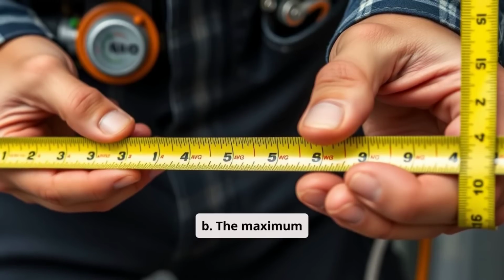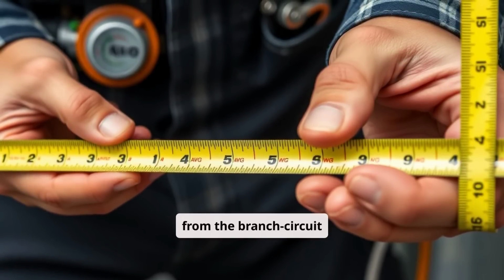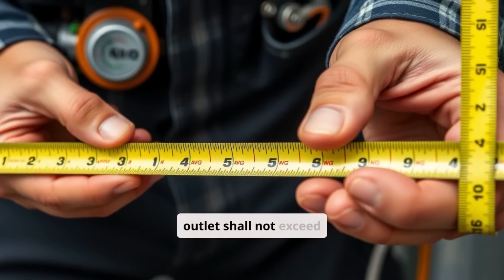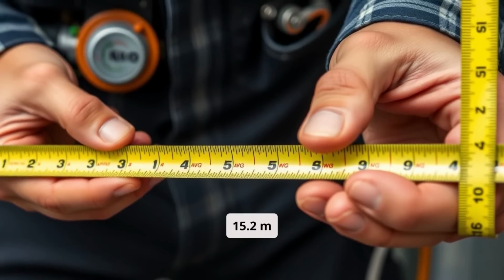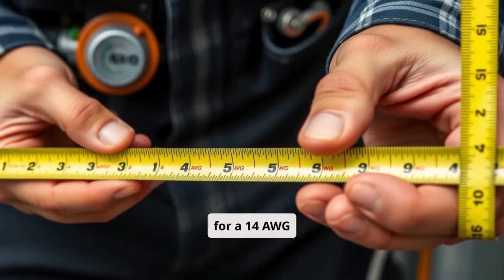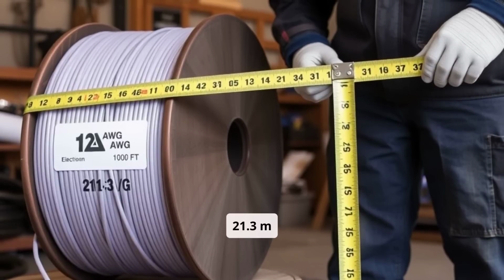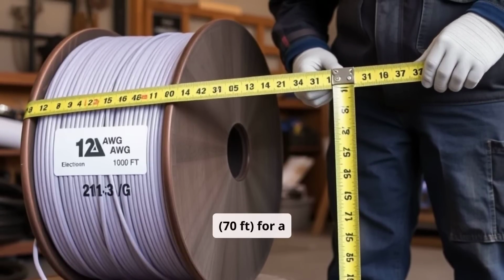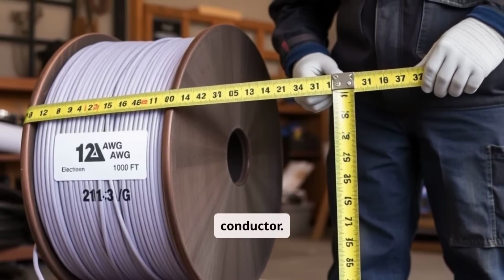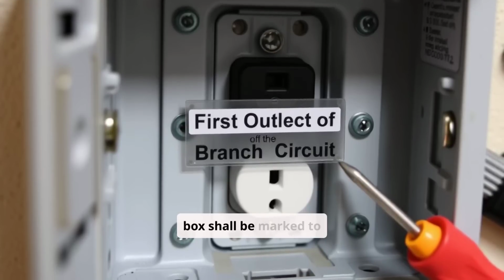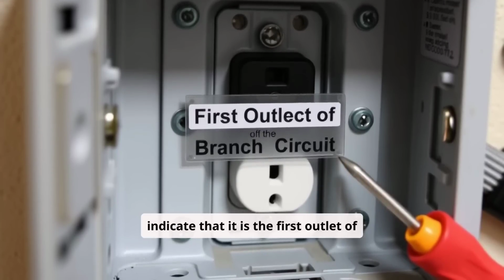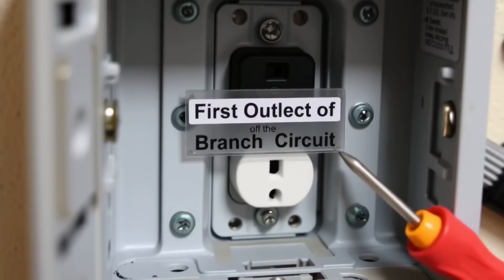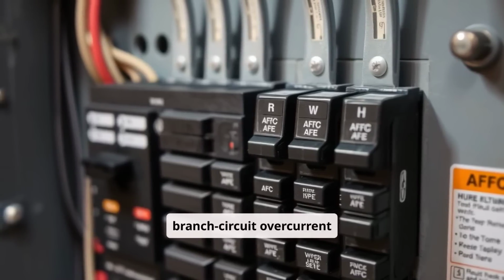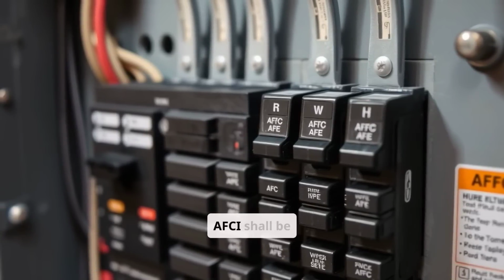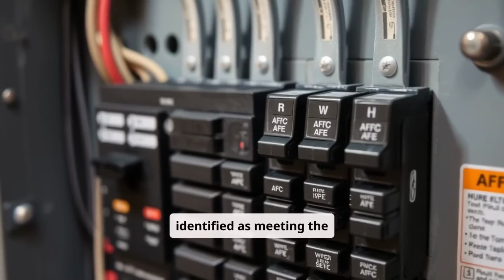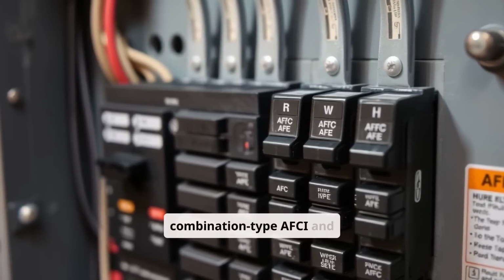B. The maximum length of the branch circuit wiring from the branch circuit overcurrent device to the first outlet shall not exceed 15.2 meters, 50 feet, for a 14 AWG conductor or 21.3 meters, 70 feet, for a 12 AWG conductor. C. The first outlet box shall be marked to indicate that it is the first outlet of the branch circuit. D. The combination of the branch circuit overcurrent device and outlet branch circuit AFCI shall be identified as meeting the requirements for a system combination type AFCI and listed as such.